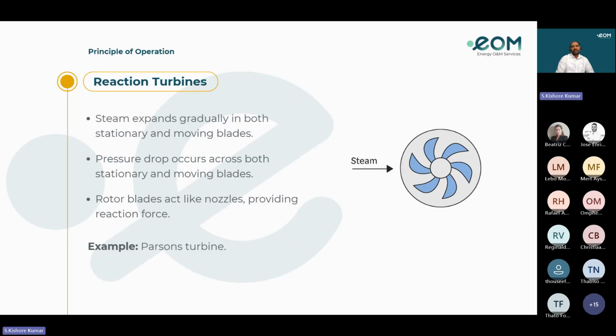Reaction turbine. A reaction turbine is a type of turbine that generates torque through both the pressure and kinetic energy of a fluid. Here, the steam expands gradually in both stationary and moving blades. Pressure drop occurs across both stationary and moving blades, and the rotor blades act like nozzles, providing reaction force. Examples are the Parsons turbine and Francis turbine. It is used in both larger capacities and small retrofit projects.